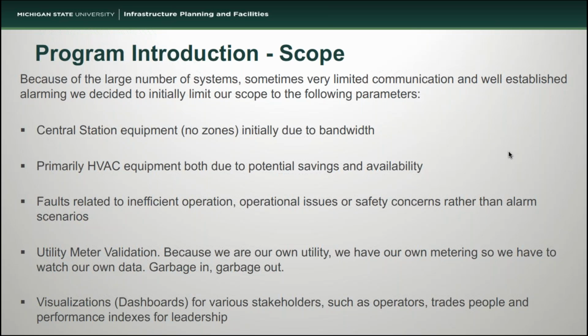Once we started looking at what we could do with our fault detection system, we realized that we really needed a utility meter validation system, and we're using our fault detection platform for that. Because we are our own utility, the vast majority of our meters on campus are our meters, so we're watching that data, and we wanted to automate that process so that we can catch inconsistencies in the reported data more quickly. And then finally, because we have a lot of stakeholders that are involved, we wanted to be able to build our own visualizations. Our operators in the control room have different needs than the tradespeople, and then our leadership wants to see different things than what is useful for the operator and the tradespeople. Next slide.